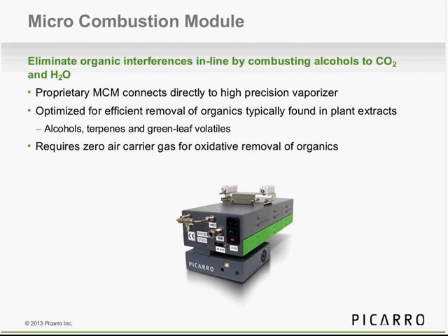Micro-combustion module, I will touch on this again in a minute. This is a very important addition to our vaporizer that allows you to be less concerned with organic interferences from contaminated waters. For example, plant waters, which are known to have alcohols, ethanol, methanol, can interfere with the spectroscopy for any laser-based technique. The micro-combustion module is a way of dealing with that, and I will talk about this a little bit more in a few slides.